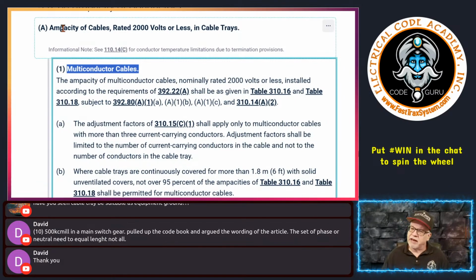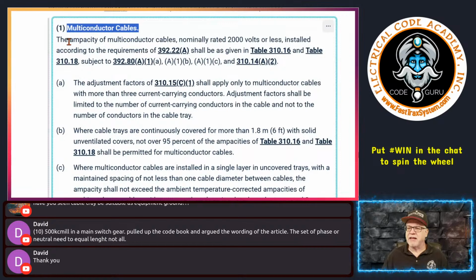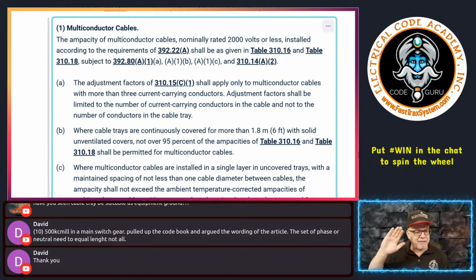So if you look at it right here, it says the ampacity of multi-conductor cables nominally rated 2,000 volts or less, and we're not going to do medium voltage on my show. Okay, not my bailiwick, not my thing. Even though Prysmian has medium voltages, I'll leave that to their people. I can answer questions on it, but I'm not going to do that in my show. I'm going to talk about what we use day in and day out, typically 2,000 volts or less applications. Okay, installed in accordance with the requirements of 392.22(A).